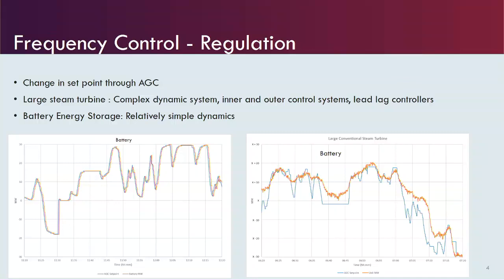This slower acting frequency control is delivered through a control system which AEMO runs and operates, called Automatic Generation Control, or AGC. It controls a number of units in the NEM, pulsing them up or down in response to slow movements in frequency. If frequency is a bit too high, it'll start pulsing units down; if it's too low, it'll pulse units up.